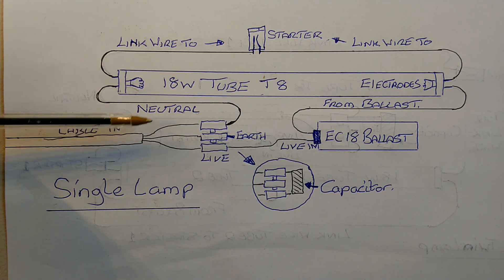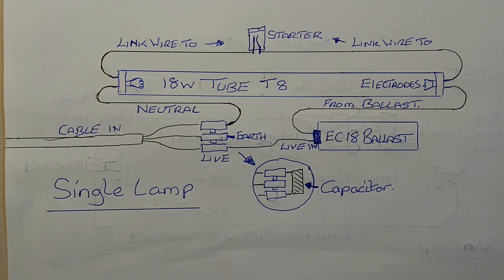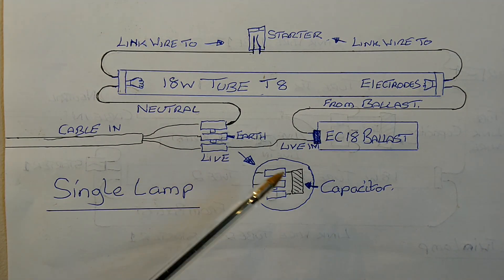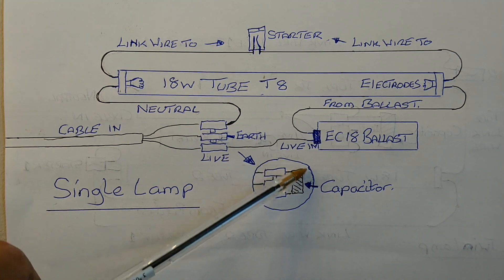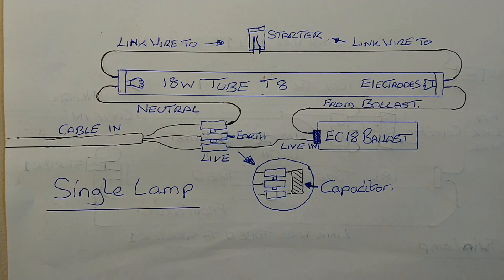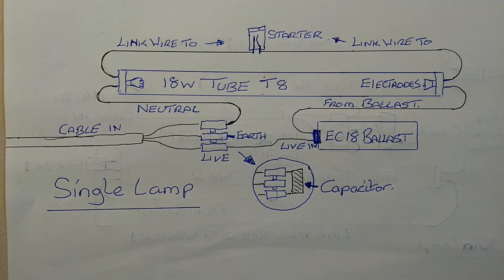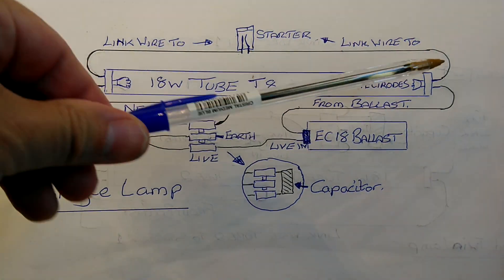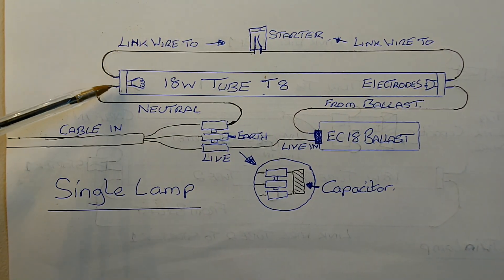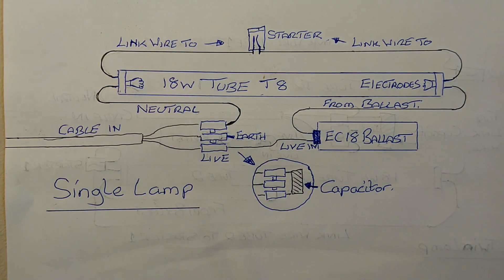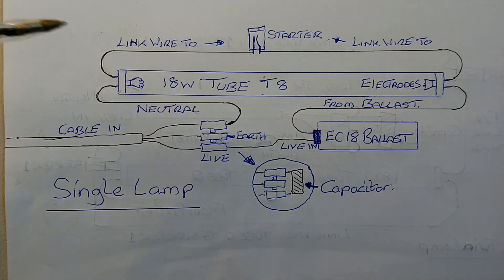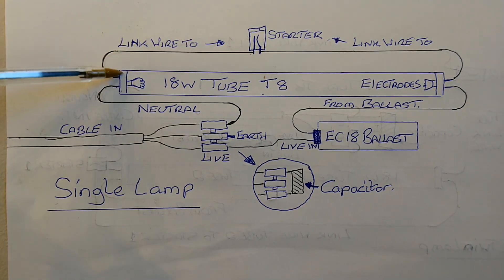We have a capacitor crossing between live and neutral, a smoothing capacitor. And then the live goes into the ballast. From the ballast it goes to this end of the fluorescent light, and the neutral returns from the opposite side of the fluorescent light back to the connector block.